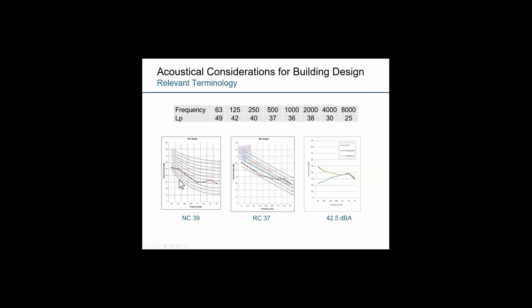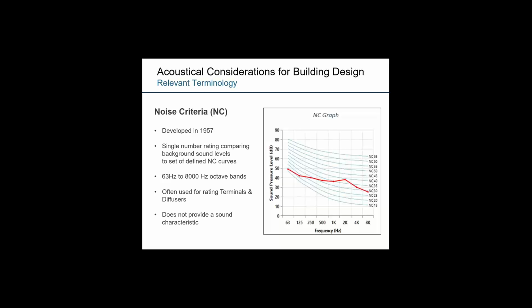If you take those sound pressures and plot them on a standardized set of curves, this is how you typically obtain those single number references, like the NC, for example. NC, or noise criteria, which is really the most common one that we see being used, takes those 8 octave bands, and if you look at the red line on the curve, once you plot them, the highest curve that is crossed would set your noise criteria. In this case, it looks like about 2000 hertz would yield roughly NC 40, as that would be the highest point on that curve, and now your 2000 hertz octave band would be setting your NC 40 criteria for this example.